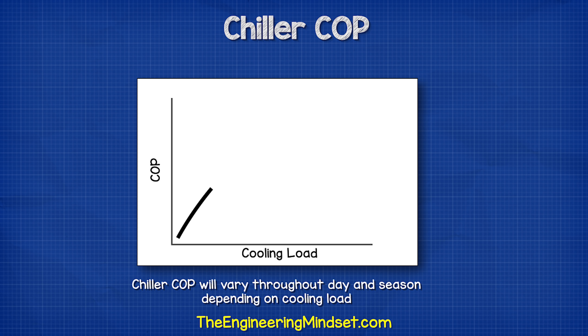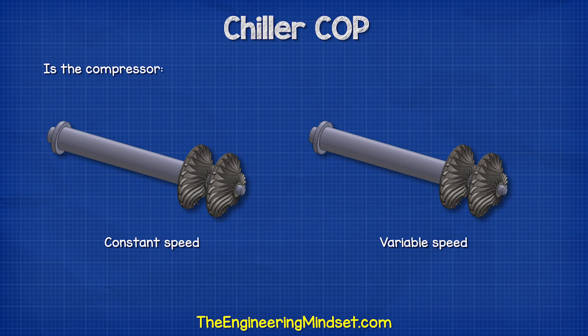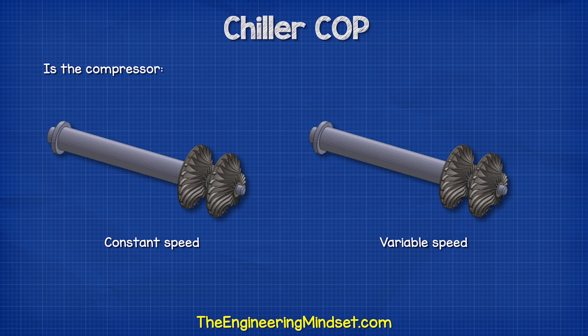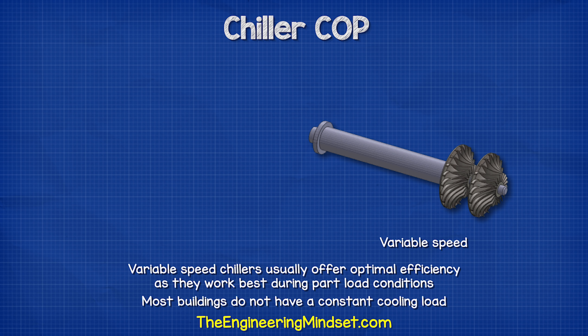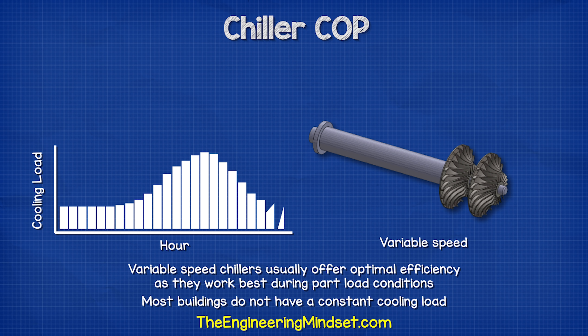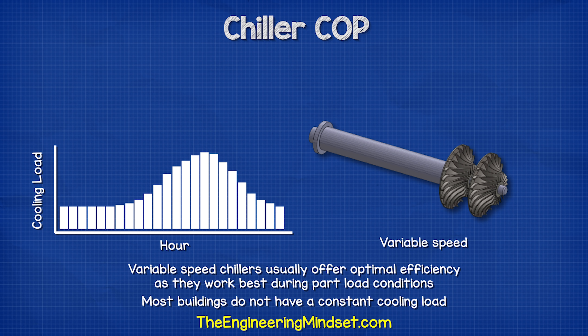The COP of a chiller will vary throughout the day and the season — it is not a fixed value unless it handles a constant load, which most buildings do not. One of the biggest impacts on these values is whether the chiller's compressor is constant or variable speed. Variable speed chillers usually offer optimal efficiency because they work best during part load conditions, and most buildings operate at part load for the majority of the year. There will only be a few days or weeks per year, usually in the summer, when the chiller is operating at full load.